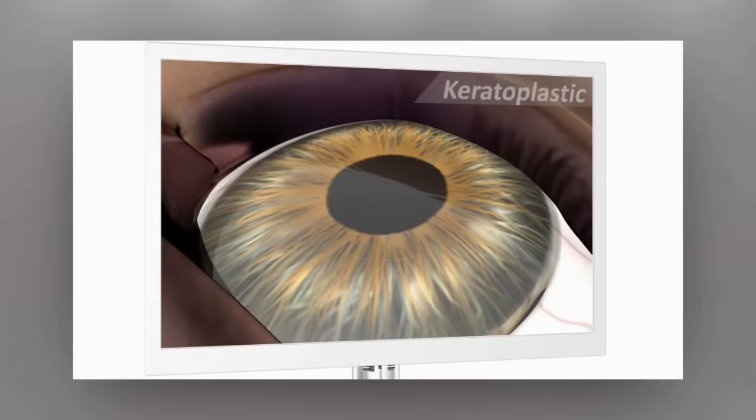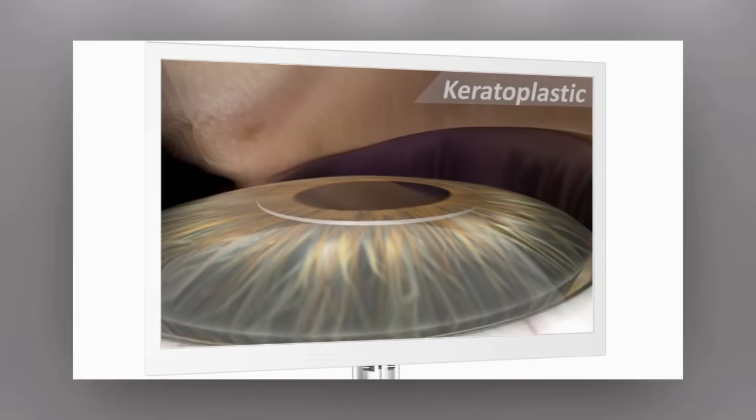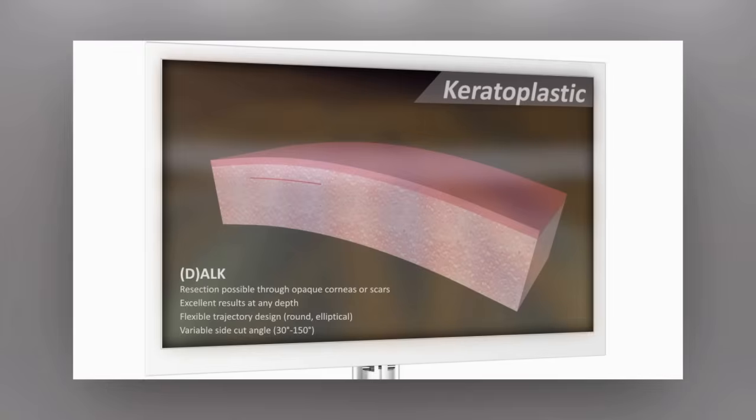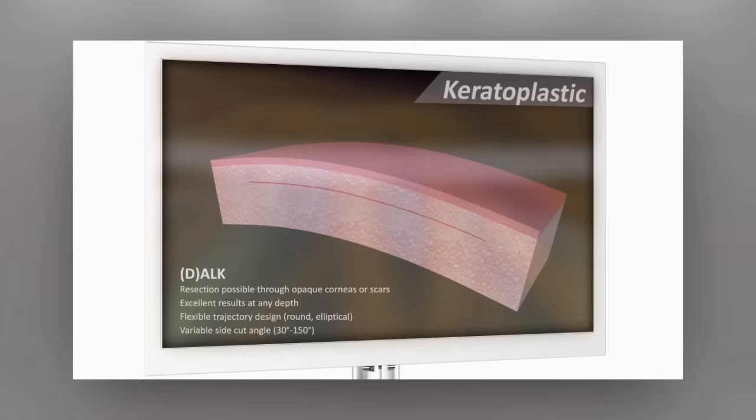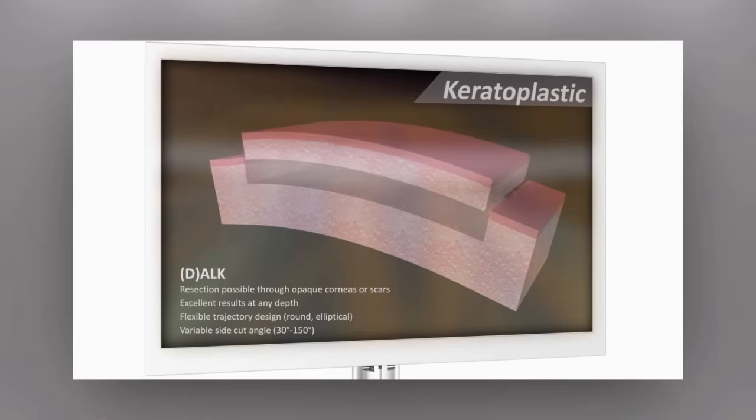Lamellar or penetrating keratoplasties are often procedures of choice, where diseased corneal tissue must be replaced with a graft of donor tissue. Flexible trajectory designs, round or elliptical, and variable side cut angles from 30 to 150 degrees are possible. With the Femto LDV's cutting performance, precise beds may be prepared even in the presence of opacified or scarred tissue.